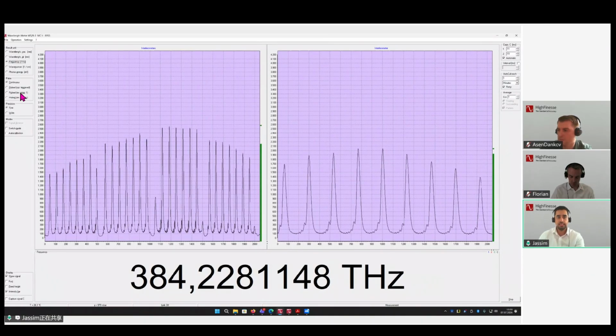If you have ordered the trigger option in the beginning, because this is something that has to be implemented inside the wavelength meter, you will find two modes for the trigger. The goal here is to synchronize your measurement with an external trigger, and you have two modes. The main difference between the two modes is that in mode 1, once you send a TTL signal, this is where your measurement will start. And when you send the other signal, this is where your measurement stops and the next measurement starts. Mode 2 is different. When you send a signal, yes, the measurement starts, but it will use the exposure time that you have already set in the software.